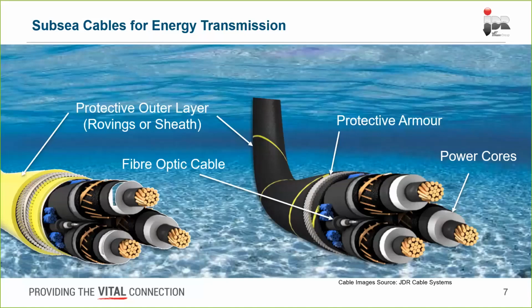That's why dynamic cables have more armour, contrahelically laid to give more torsional balance, along with protective sheaths offering more abrasion protection. In terms of size, we're talking about 70 millimetres up to about 120 or 200 millimetres, so a range from just bigger than a tennis ball up to a football or bowling ball size. The size varies drastically, but the more we supply, the greater the demand for power, and we're supplying cables in the larger ranges.